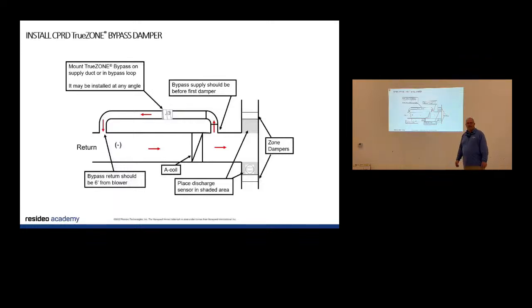Why do you need a bypass again? Let's say I've got 3 zones, and I've got a 2000 CFM system, but I have a master bedroom that can only take 400 CFM, and the other 2 zones are closed. I have to get rid of that air somewhere. Otherwise, the motor's going to amp up, and I've even seen it where the motor blower wheel has been blown apart because there's so much static and air in that system.